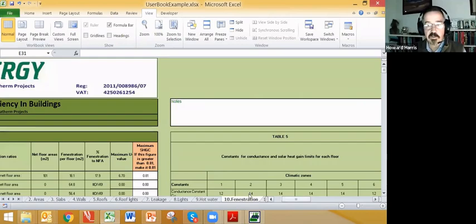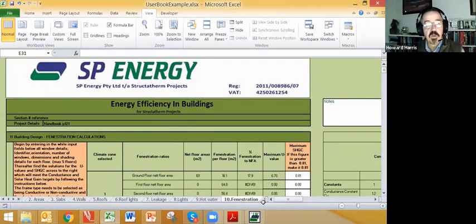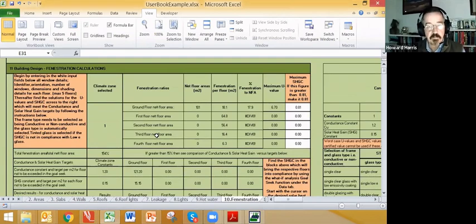So if we go back up to the top of the table, we can see how that input impacts the results. We have, as previously calculated on tab 2, the net floor area of the building. We see that there's 16,1 square meters of fenestration at 17.9%, and it automatically throws up a U value requirement for that configuration of glass at 6,7.